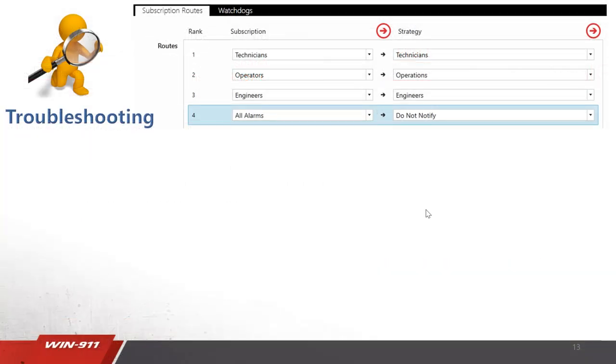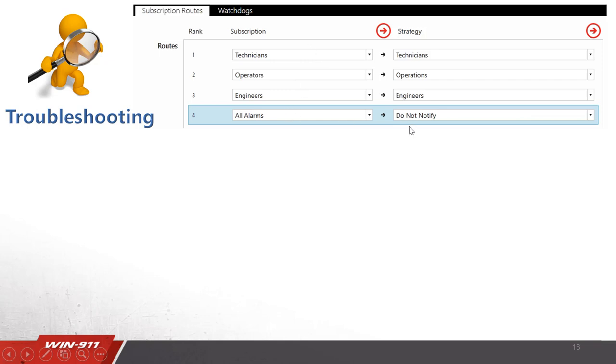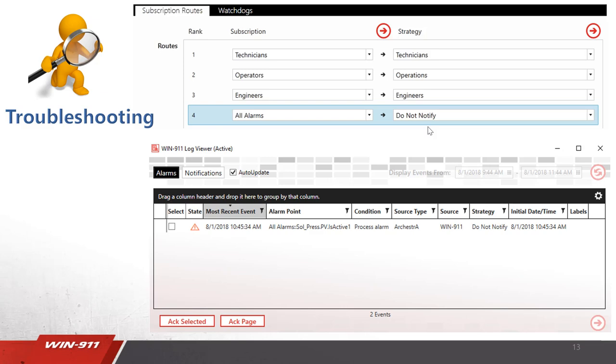Let's revisit the troubleshooting using the all alarms filter that we made earlier. This subscription route went down the line one, two, three, and finally if alarm was caught, the do not notify. What can you do with that? Well, using log viewer you can pull up to see alarms that went to the do not notify strategy. Why would you use this? Why would alarm be filtered through?